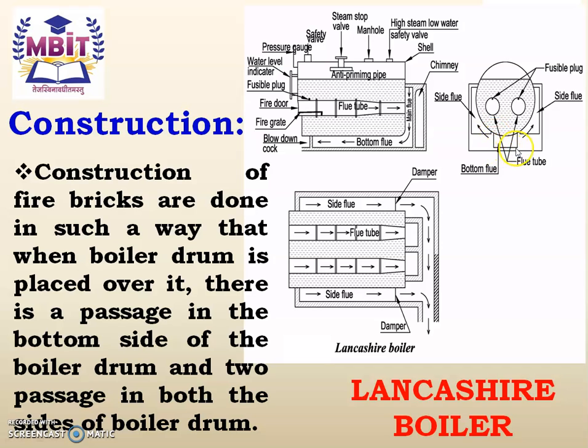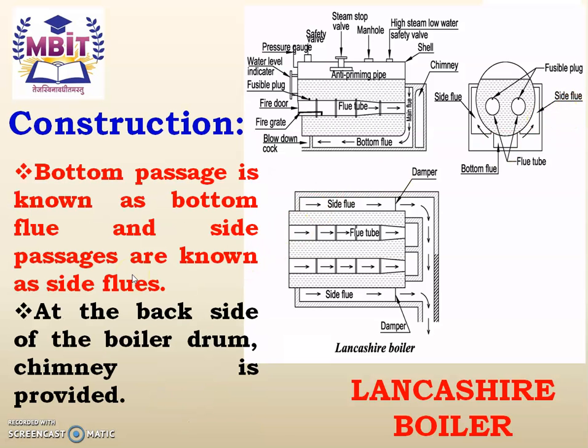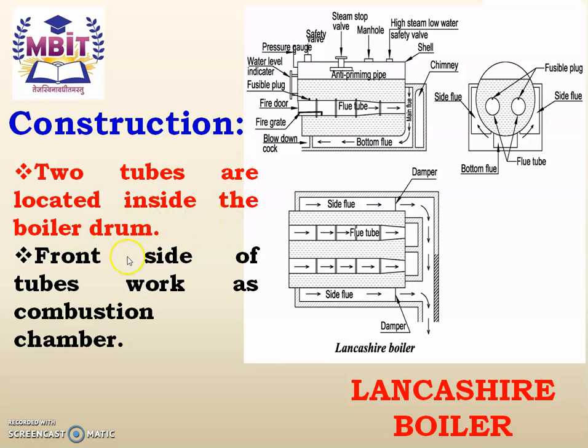The passage at the bottom side is known as the bottom passage or bottom flue, and the two passages on the sides are known as side flues — the left hand side flue and the right hand side flue. At the back side of the boiler drum a chimney is provided. Two tubes are located inside the boiler drum, and the front portion of the tubes works as a combustion chamber, where the fire grate is provided for burning fuel.